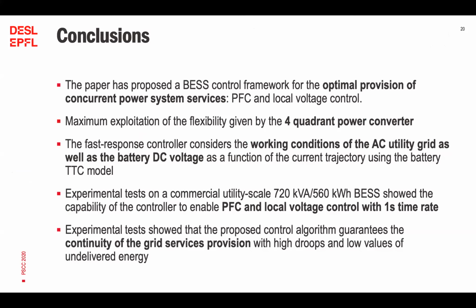To conclude, the paper has proposed a BESS control framework for the optimal provision of concurrent power system services, namely primary frequency control and local voltage control. The proposed controller considers the working condition of the AC utility grid as well as the battery DC voltage in order to be aware of the actual capability of the employed power converter. The experimental test on a commercial utility scale battery showed the capability of the controller to enable primary frequency control and local voltage control within 1 second time rate.